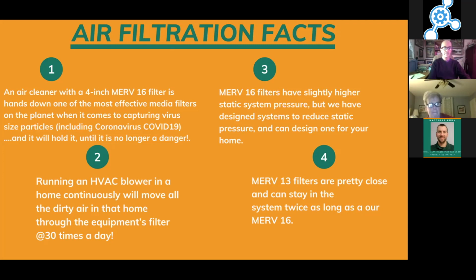When you start getting into that MERV 16, there's a couple of other things you have to consider, like airflow, because the filter is so good at filtering out stuff. Air also has a harder time flowing through those filters. So usually once you get into that, you have to start taking some airflow measurements. So it's not as simple as, hey, let's take this filter out and put a MERV 16 filter in here. However, MERV 13 is very, very compatible, very close to a MERV 16, and that 13 filter will do a very, very good job, as we've seen from some of these charts.